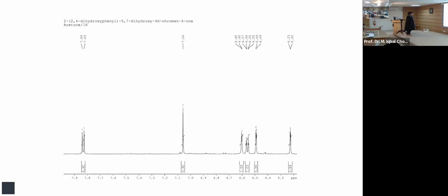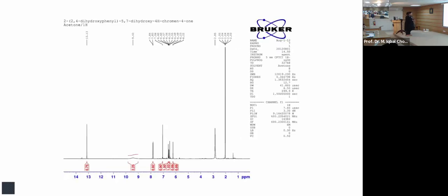Okay, so now another important thing, the spectral width, that you have to define, right? Here you define the spectral width, I think it's from -1 to 15 ppm. But that spectral width you have to define. It doesn't take it automatically. You have to write the spectral width when you are doing an NMR experiment by yourself. And then you have to select the middle point as well.